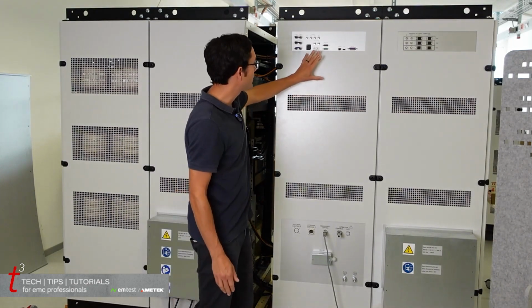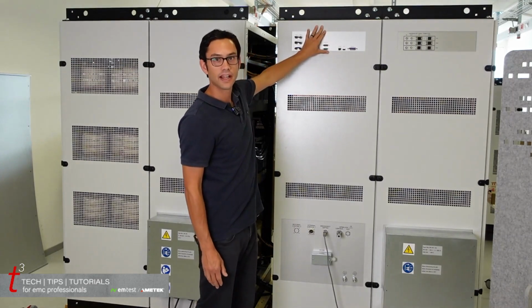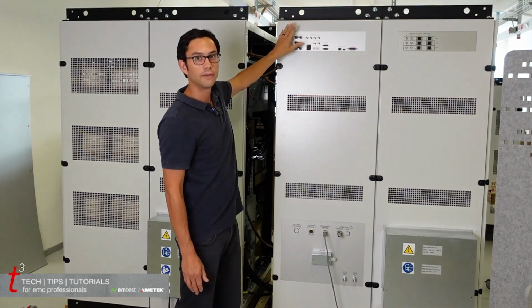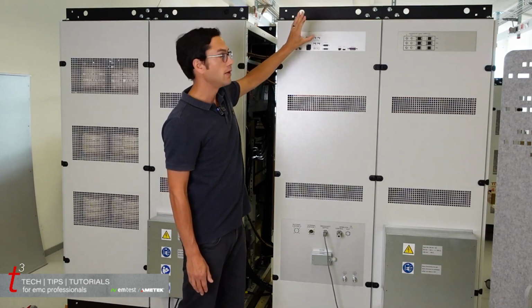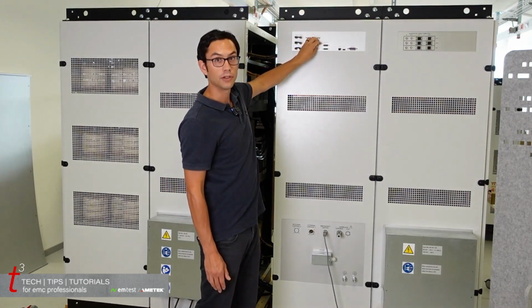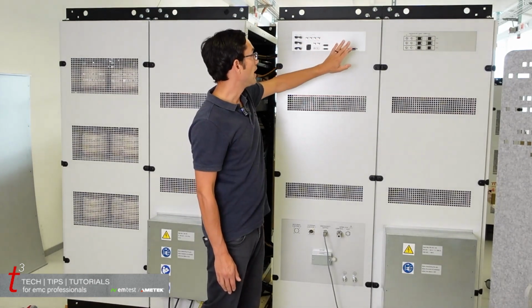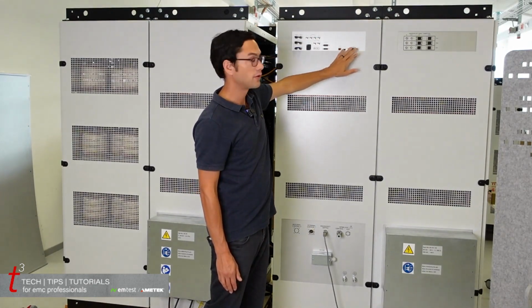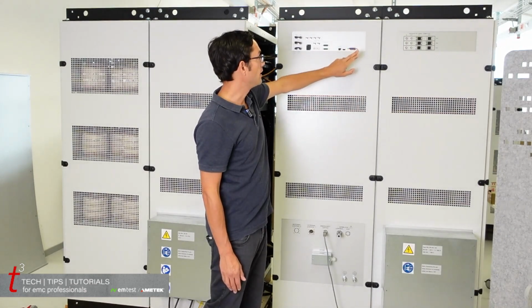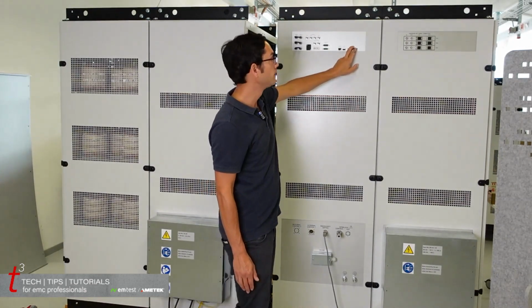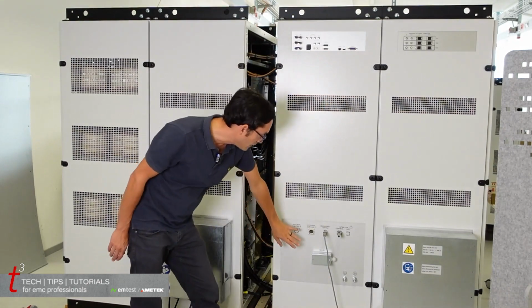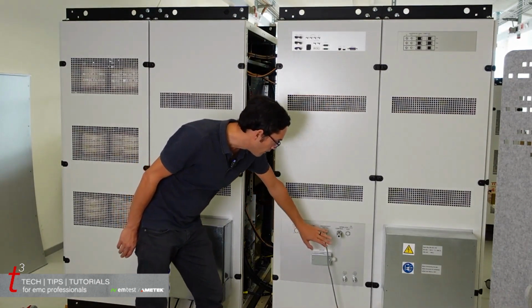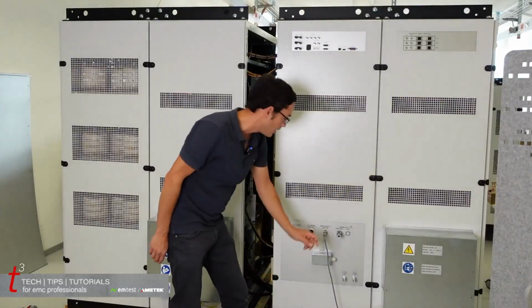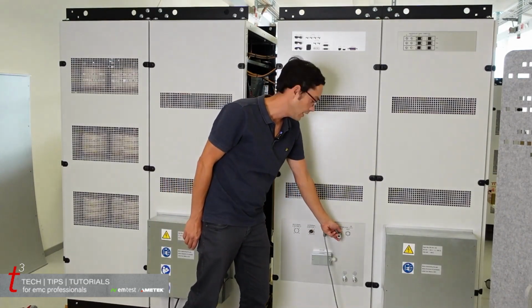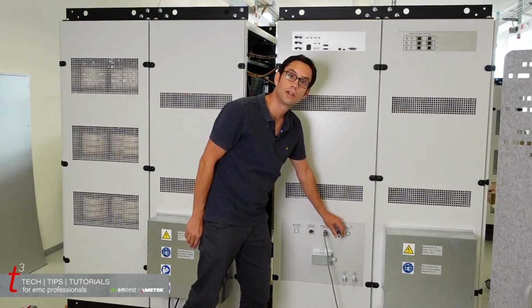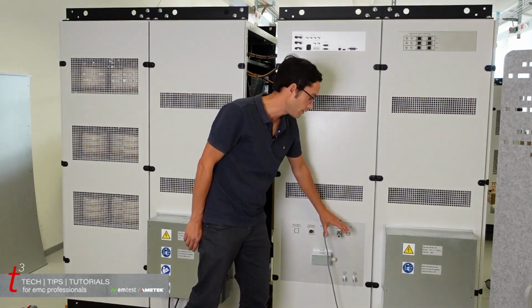In this cabinet, in the top, this is the backside of the control unit. Here we have the analog control signals, the trigger input outputs, the monitoring input and outputs. We have the remote control connectors, Ethernet and IEEE 488, so GPIB. On the bottom side we have the analog connector panel where we connect the emergency switch, and also a separate interlock circuit, which is explained in more detail in a separate video.